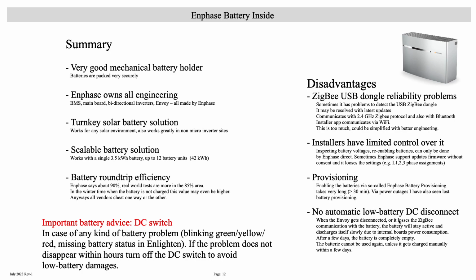However, if the customer is on vacation and there's a problem with the battery, and they come back two weeks later, the battery is off and dead, that's a serious problem. It doesn't have to be dead, but we can get to that point when there's a problem for weeks and nobody detects it.